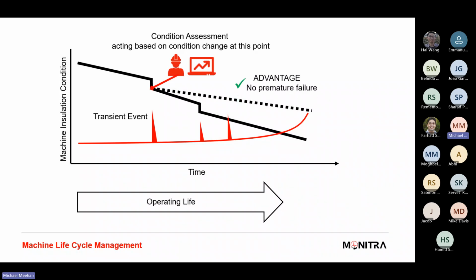So as we get that advantage of extended life, we can do that through routine inspections. I mentioned visual inspection earlier, some of the more simple and basic ones. Temperature monitoring we've mentioned, bearing condition monitoring, and all these are routine offline type inspections. But what we want to try and do is go to a more preventative and condition-based approach.